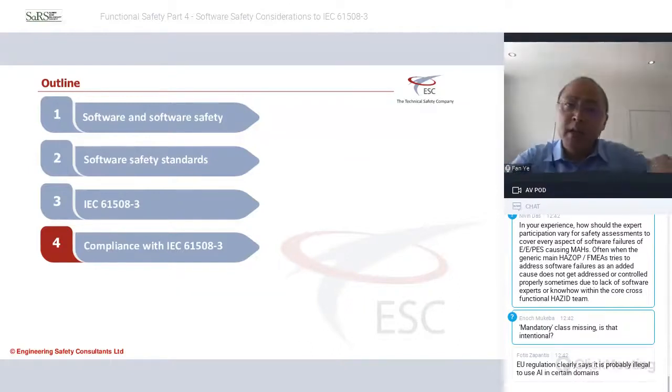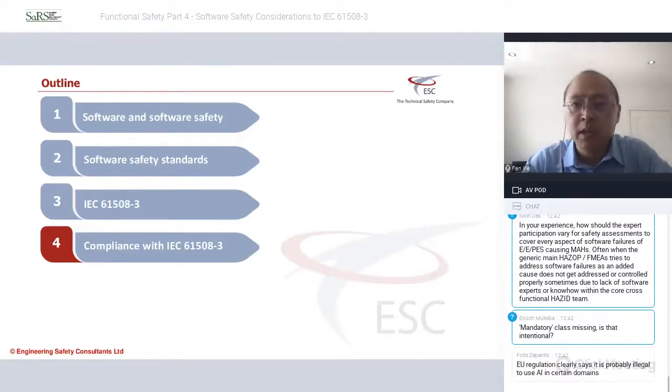As I said earlier, it's the generic, basic functional safety standard. You'll find that the requirements from 61508 are very similar to requirements from industry standards in other domains, such as the rail industry, even EN 50128. You'll find very similar requirements, and even DO-178C has many similarities, because from a software design perspective, you need to apply a rigorous process, employ competent people, and have a rigorous V&V, verification and validation, process in place to make sure that we're not introducing any systematic faults into the system.